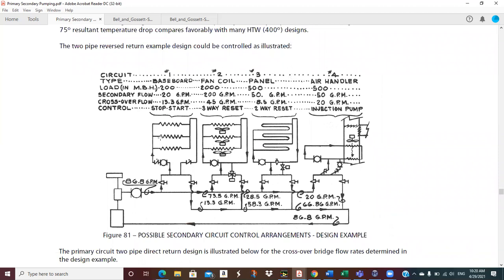And so then, the difference between crossover and secondary is going to mix right in the common pipe. And that's what's going to modulate the temperature that goes out to the secondary. And so he's projecting to do this baseboard control with start stop, just click the pump on and off. For all of these fan coil units, there's a bunch of them because that's a lot of flow for fan coil units. We're going to do three-way valve control, and see it's in the crossover with reset that temperature with outside air.